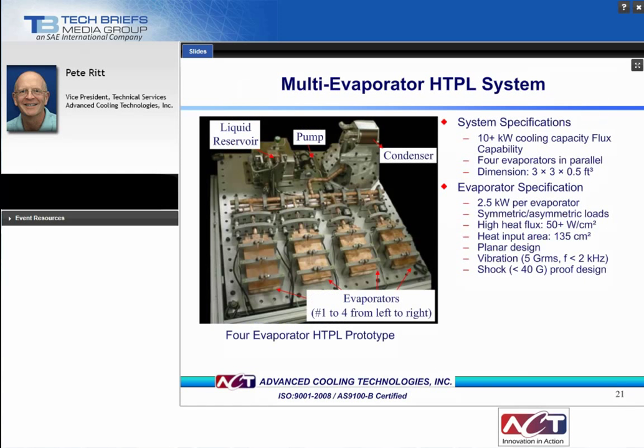Here is a picture of a hybrid two-phase loop. This one has four 2.5 kilowatt evaporators, which can be seen in the lower part of the picture. System and evaporator specifications for this 10 kilowatt cooling solution are noted on the right. Of equal importance, the system has passed rigorous shock and vibration testing while delivering the high heat dissipation levels.